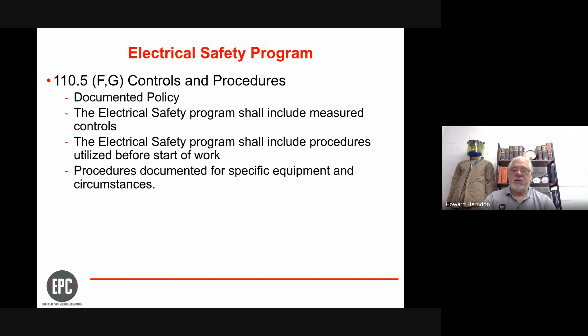Often our customers don't understand the process, because if something blows up, putting a breaker in a panel may be a 30-minute or an hour process. But if it blows up, the best I can probably hope for is a 4 to 8 hour shutdown to change that panel out and get them back online. What are they going to do during that 4 to 8 hours? So having controls and procedures documented for the specific equipment and circumstances is extremely important.